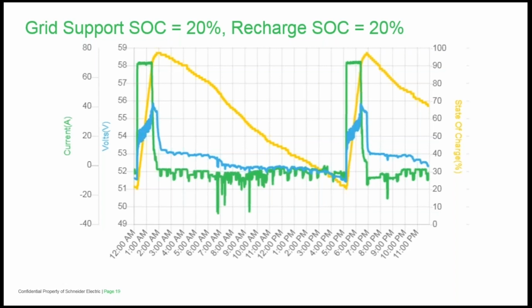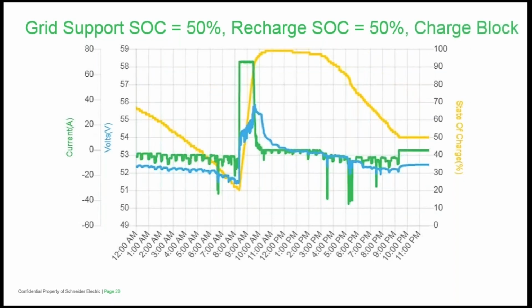I can use charge block to block charging during the more expensive periods and charge when the rates are lower. So therefore, you can do arbitrage that way. You can export power during a certain period with the sell block function to minimize loads that are occurring during a specific period of time, or you can even export power back toward the main panel during that specific period of time. So you have a lot more options available to you with the Pro and state of charge control. Note that the charge block feature will block charging during the periods when the rates are higher.